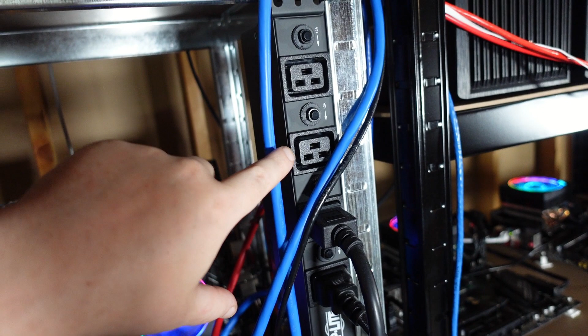You can just times 12 by 240, and that'll tell you the wattage you can get out of here. You do usually find these plugs on any power supply around 1500 watts or higher. Once you start getting into ASICs, you're gonna have to start looking for conversion plugs to go from C13 to C19 if you get a PDU with strictly only C19.